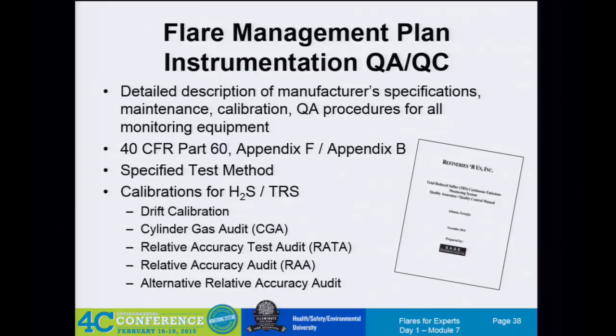For the instrumentation, you're going to need a QA/QC plan that's required under Appendix B and F, and this is just a good place to document what's your QA/QC process. It's a good thing, so then you can also have an easy way to talk to your I&E guys and say, okay, this is why we're doing the daily cals, why we're doing cylinder gas audits. Are we doing an alternative RATA versus doing a full-fledged RATA? This is a nice place to document that, so everybody's on the same page.